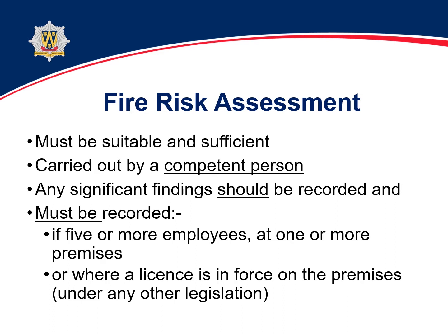Or if there's a licence in force on the premises under another piece of legislation. Again, for those who know Shrewsbury, up from the fire station, there's a large shipping container placed on land next to Quickfit that sells fireworks around about September, October every year. Now, there's only one person working in there, but they have a licence to sell fireworks issued by the local authority. So in this instance, they must have a recorded fire risk assessment.